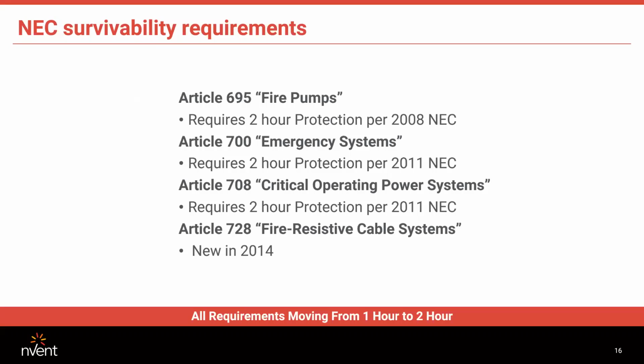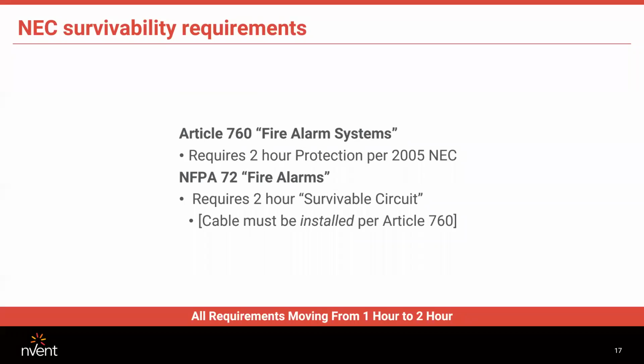Now, Article 695 requires 2-hour protection, and it's been required as far back as the 2008 NEC. So any fire pump feeder, both normal and emergency, is required to be fire rated for 2 hours if the feeder is running through the building. Article 700 requires 2-hour protection on emergency systems, and that's been since 2011. And Article 708, which is critical operations power systems, and I'll get into that a little more in a moment, also requires 2-hour protection. That's been around since 2011. And then you have Article 728, which just expounds on the fire-rated systems that are permitted to be used. Also, you have Article 760, which gets into fire alarms and references NFPA 72, which does require a 2-hour survivable circuit for certain types of fire alarms.